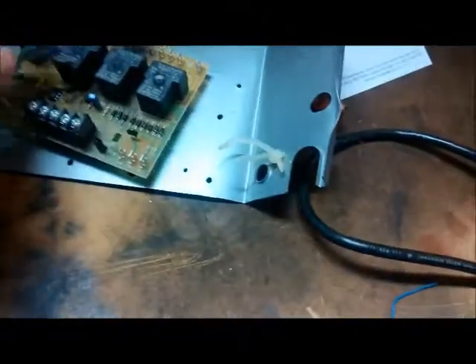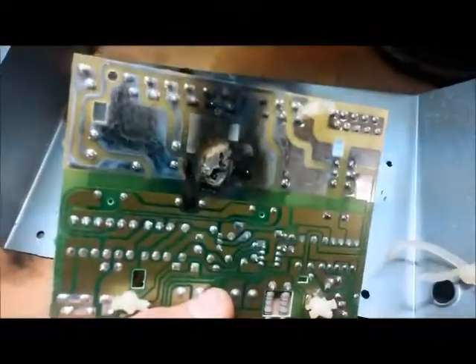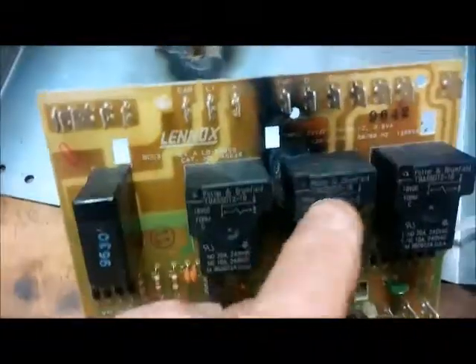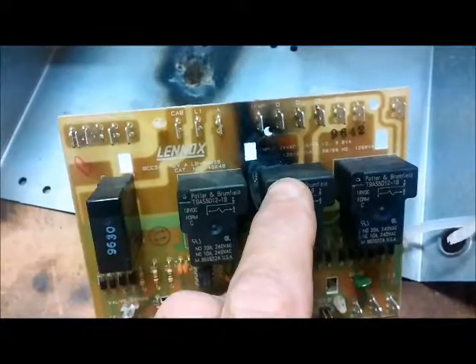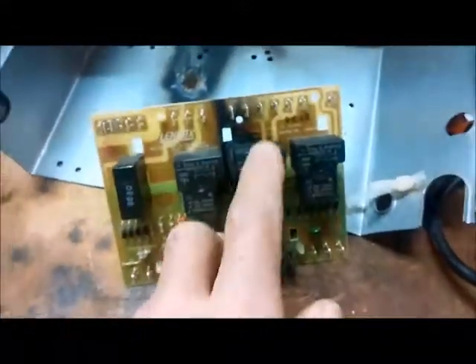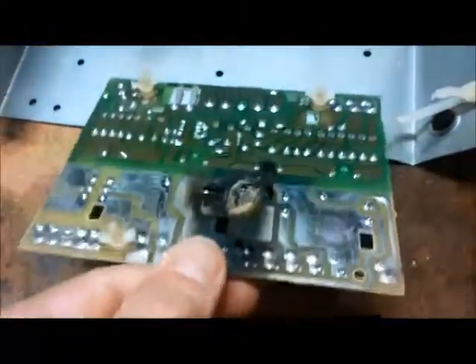So, where I've got this breaker plugged in here, I'm going to use this for test. I just took this off a Lennox. The old Lennoxes used to come with those instead of the fuse. This is a board I did last week. The fan was not turning on. Everything else worked, so clearly where that burnt spot is right there is the fan relay that turned the fan on in the heat mode. Worked fine if you just turn the fan on, but that's a pretty bad burnout there.